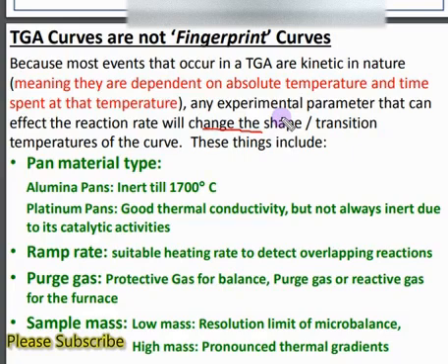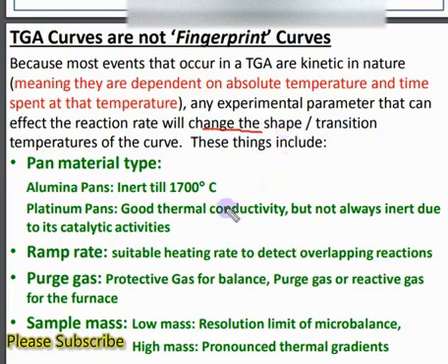For instance, a thermal event occurring at 150°C for a particular heating rate — by changing the heating rate, that event would occur at a very different temperature. That is why we say TGA curves are not fingerprint curves. We will now discuss what kind of parameters influence the experimental curves.